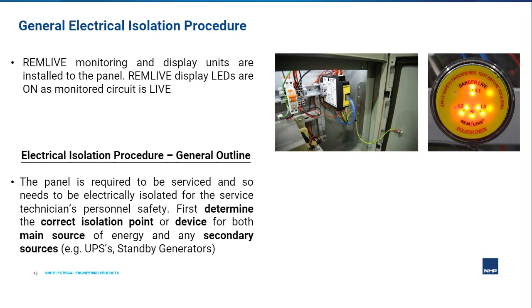Now, before isolation, it's assumed, of course, that the REMLIVE monitoring and display units are installed and wired correctly to your panel. When the system or circuit is live, the REMLIVE display unit LEDs should be on. Right, so let's now assume that we have this panel on site, it's live, and the REMLIVE display unit is indicating as it should be to provide a visual indication to the operator that voltage is present. The panel needs to be serviced, and so the service technician is brought in, and before the technician can make any direct contact with electrical components inside the panel, they need to electrically isolate the panel or circuit.